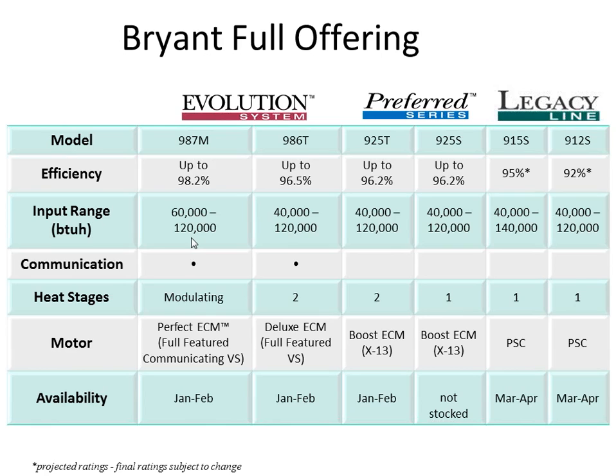In reality, it's actually a very well-staged furnace. It modulates from 40 to 100% in 1% increments, which means it's a 61-stage furnace if you want to think of it that way. But we would call it a modulating furnace, just like we call a stepped hot water valve a modulating hot water valve. These modulating gas valves are paired with variable speed indoor fan motors, and they're paired with variable speed inducer motors. As we throttle the gas back, we also want to throttle back the induced air, the combustion air, to kind of match that.